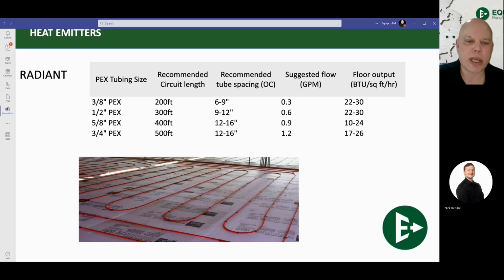This is all going to be subject to the design and installation of the system. If they're putting it on little installation board like you see here, yeah, probably going to be closer to 22 to 24. If they're putting it in those radiant panels with the little pucks on it that you can fit through, those would be 22 bang on, maybe only 21, because you're losing a bit of the surface area contact from the PEX into the gypcrete or concrete overpour. If you're using heat transfer panels, the aluminum panels, you could be 30 BTUs per square foot up to 40 BTUs per square foot. There are no rules with radiant.